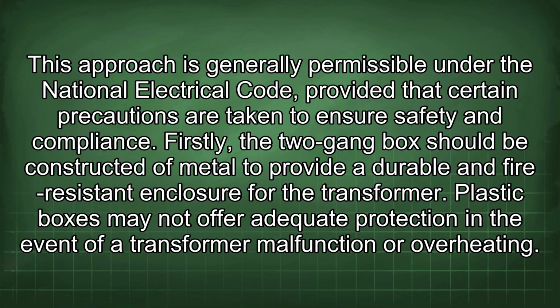compliance. Firstly, the two-gang box should be constructed of metal to provide a durable and fire-resistant enclosure for the transformer. Plastic boxes may not offer adequate protection in the event of a transformer malfunction or overheating.